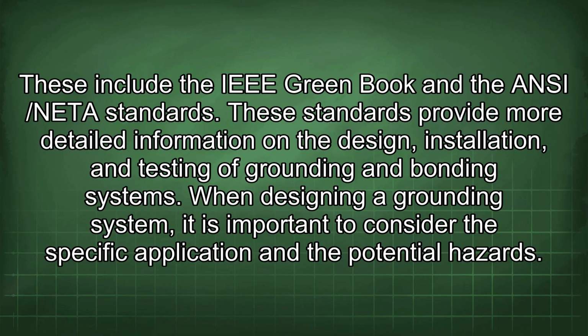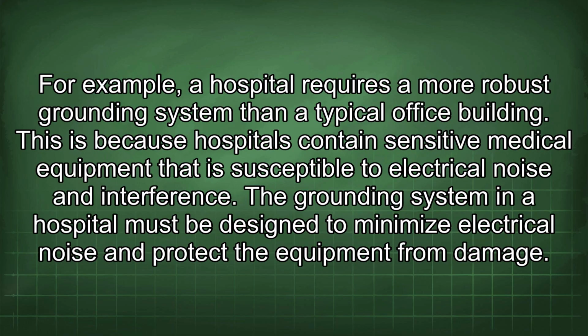When designing a grounding system, it is important to consider the specific application and the potential hazards. For example, a hospital requires a more robust grounding system than a typical office building. This is because hospitals contain sensitive medical equipment that is susceptible to electrical noise and interference. The grounding system in a hospital must be designed to minimize electrical noise and protect the equipment from damage.